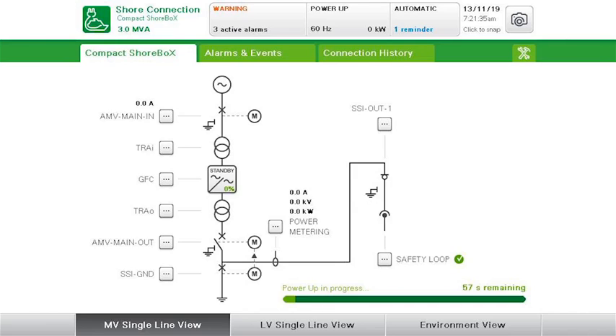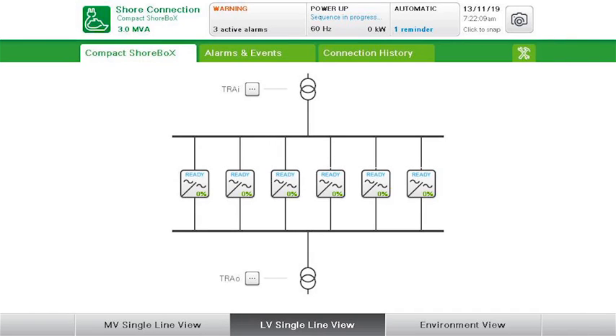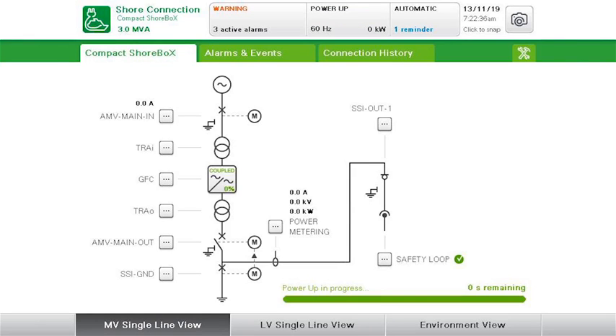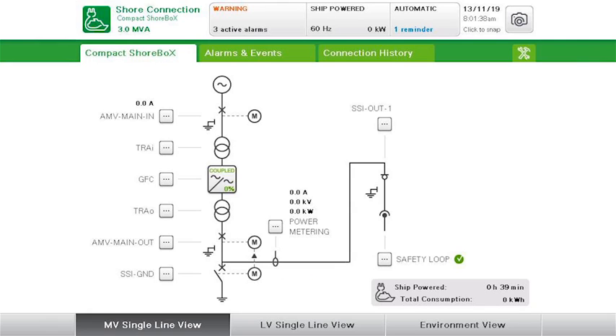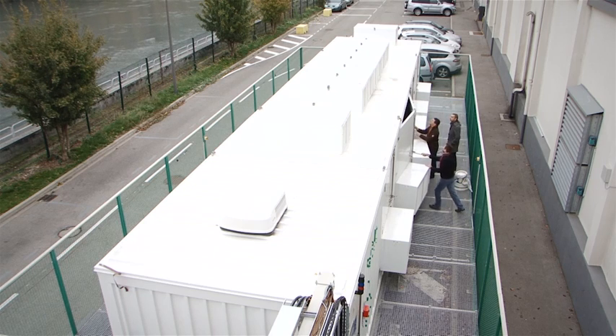First one is GFC wake up. At this point, all frequency converters will be ready to get coupled. Then one of the converters will be coupled in order to magnetize the downstream transformer. All other units will then be coupled, and the final steps basically consist in opening the grounding switch and closing the main circuit breaker. Additional features like local control of the medium voltage circuit breakers or local control of the frequency converters are only available for maintenance users.